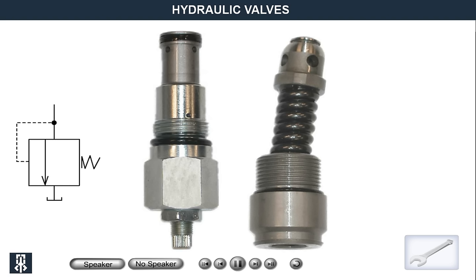A pressure limiting valve must always be in the pressure line from the pump. The valve is most often placed as the first component after the pump, thus protecting all functions that are supplied by the pump. This type of valve can also be found in other places in the system, but then with another name and a slightly different purpose.